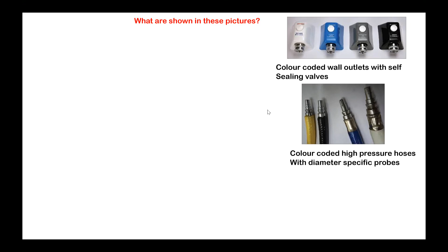So color-coded high-pressure hoses with diameter-specific probes. The diameter varies for each one. That is why you cannot insert an oxygen probe into the nitrous oxide outlet or nitrous oxide into the oxygen. And this is the probe in close-up view. This is how it will look. So this portion goes into that. This is the hose which will be fitted here like this. This metal part is called the ferrule. So, close-up view of the probe.